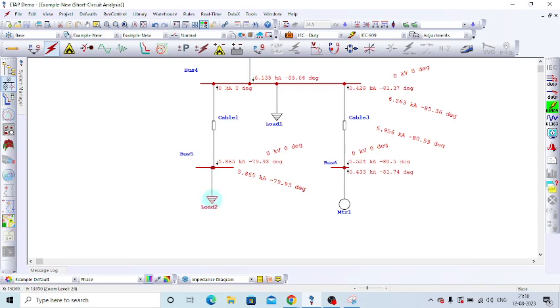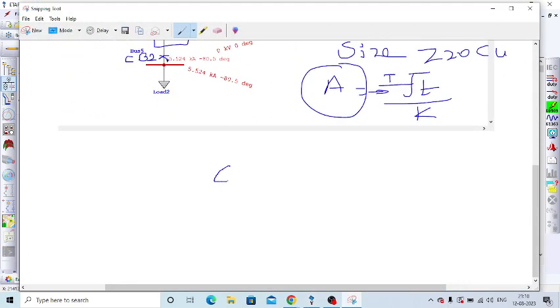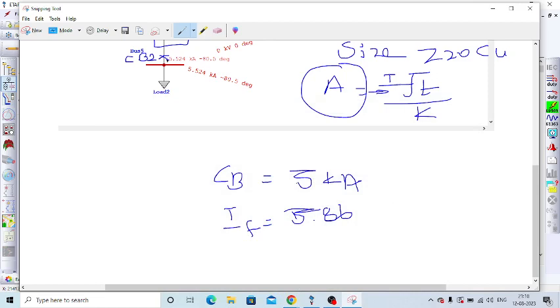Let's assume the circuit breaker used in this location is 5 kiloampere. The present short circuit current is 5.865 kiloampere. So the circuit breaker rating is 5 kiloampere, but the available fault current is 5.86. Is this circuit breaker rating acceptable? No. When we compare with the fault current, the circuit breaker rating shall be above the fault current. So the minimum rating of the circuit breaker has to be 5.86 or above.